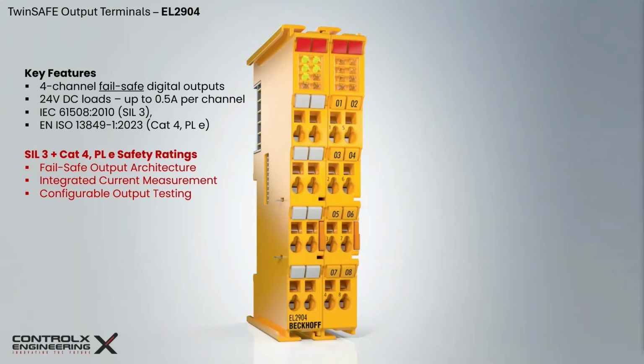The terminal supports test pulses and output channel testing that can be enabled via safety parameters. These tests detect stuck on outputs, stuck off outputs, output transistor failures, and wiring faults. Thus, this diagnostic coverage is essential for SIL 3 and Category 4. The EL2904 does not store its own safety parameters. Instead, they are downloaded from a safety logic device at startup. This provides verified and validated safety configuration, protection against tampering, guaranteed startup state, and cyclic safety monitoring via FSoE. FSoE ensures CRC-protected communication, sequence counters, timeout monitoring, and safe state enforcement on communication loss. This communication integrity is part of the SIL 3 safety chain.